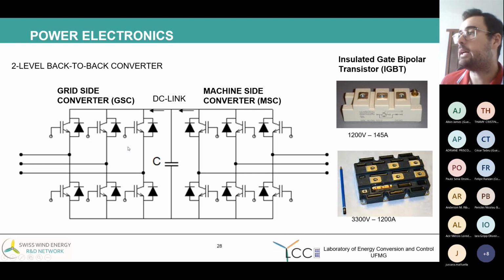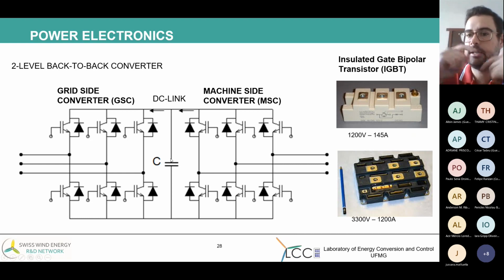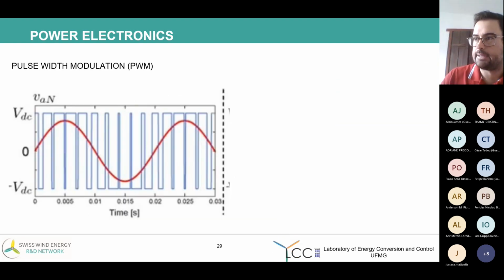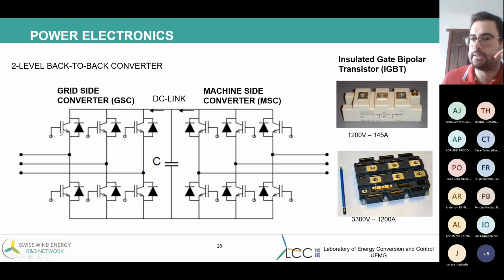In these IGBTs, it's a semiconductor. What does that mean? They work as a switch. A switch can have two states, either closed or open. So the way that the power converter works is by switching the semiconductors. The control system will control the IGBTs to be connected, disconnected, closed, open. What does that mean? Current flowing or current not flowing.